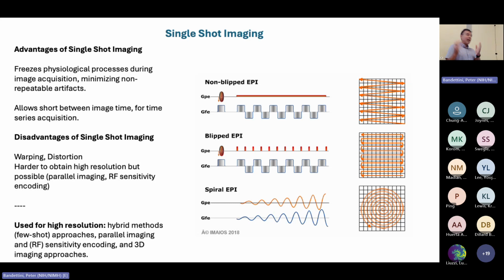That's critical, not only because it's fast and you collect a time series of images, but because physiologic motion can alter the phase of any one line of K-space. If these lines are misaligned a little bit, it will cause ghosting in your images. That's okay, but the ghosting will be different in every single image. With echoplanar, you might have some imperfections in K-space that cause ghosting, but the ghosting is rock solid the same in every image. And that's key.